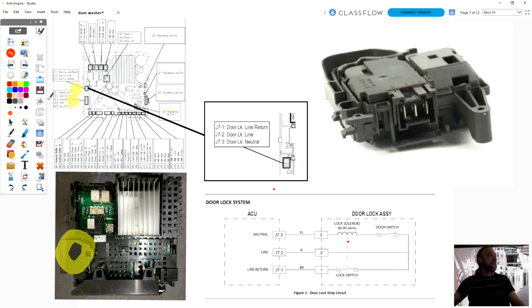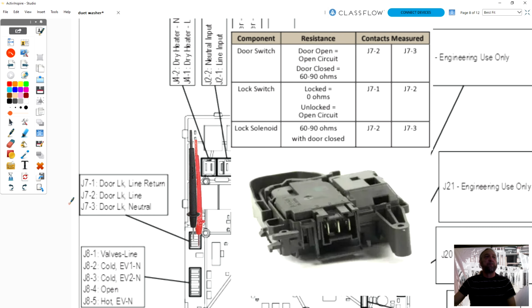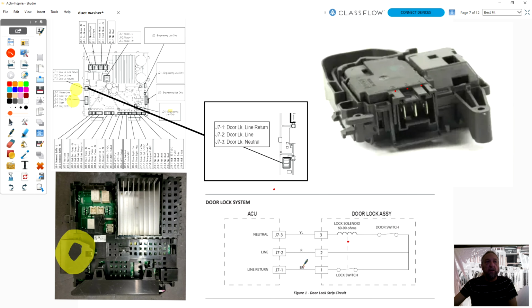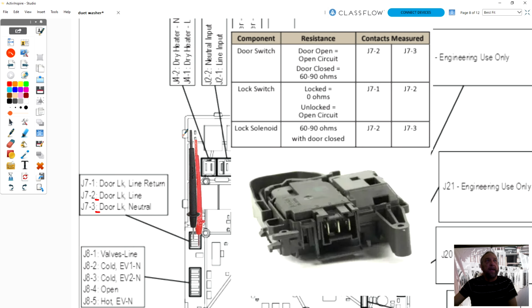I guess you guys are understanding it. Okay, so if I want to test this, it's telling me with the door open I get no reading. If I go to the board and check these 2 pins right here, I'm checking 2 and 3. If I look here, 2 and 3 are the red and brown wires coming in. So I got my meter lead here and here on the board. Between 2 and 3, if the door's open, it's open, but when the door's closed, I'm getting 60 to 90 ohms. Anybody know why?